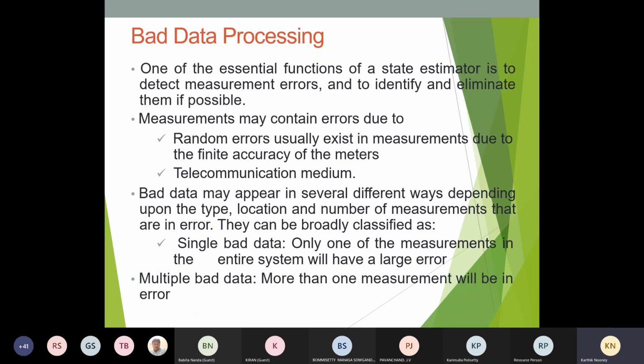We will consider the next part of our system. What exactly is bad data? Bad data means the essential function of the state estimator is to detect measurement errors and to identify and eliminate them if possible. These measurements may contain errors. In our labs also, whenever we are measuring quantities, in meters we will get some errors. To consider those errors and to exactly portray whatever the exact flow value in that part of the network, again we have to check the error for that meter and make the error for that meter 0 and restart the experiment. That means we will calibrate the meter there.